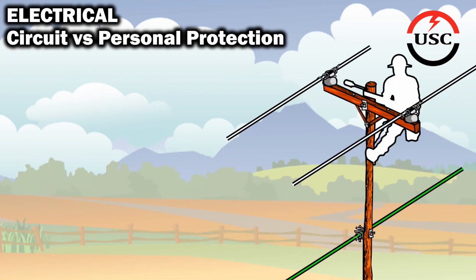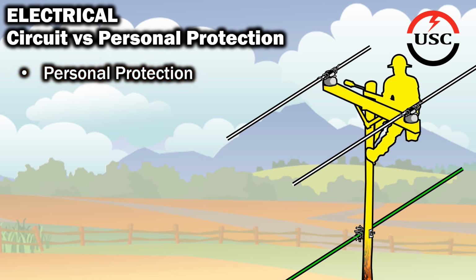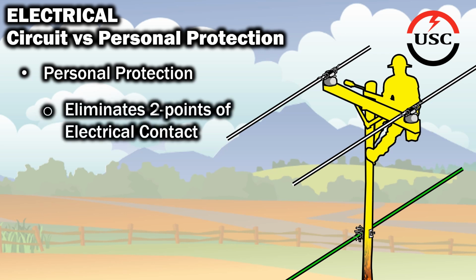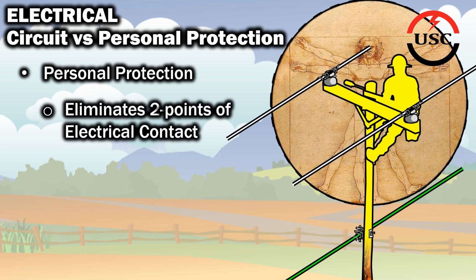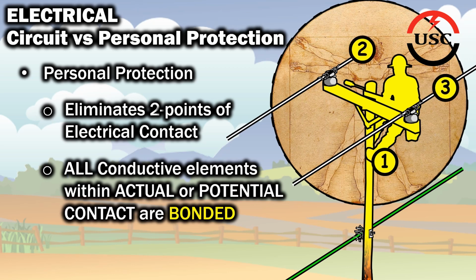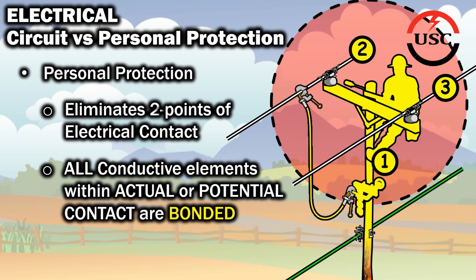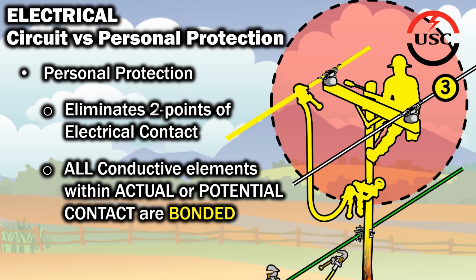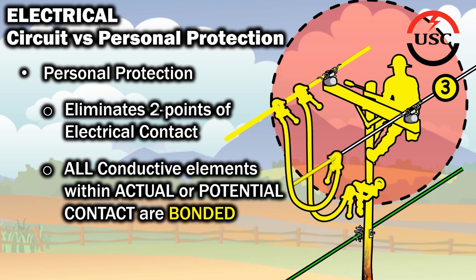Now that we've identified all sorts of ways and methods that can kill the worker, let's refocus on how to protect the worker. Personal protection is achieved when the electrical jumpers are arranged so as to eliminate 2 points of electrical contact exposure for the worker. This requires that all potential points of electrical contact within actual or potential reach of that worker must be electrically bonded to ensure that there is only a single electrical exposure potential to the worker. At this point, everything is bonded. Nothing is grounded. Now, this is good, but it isn't great.